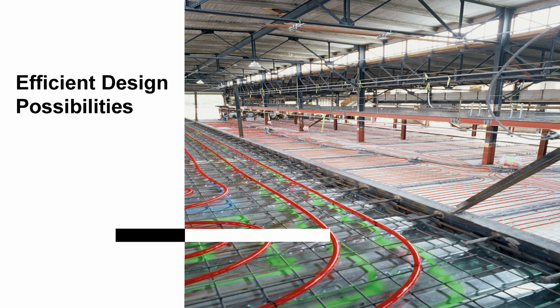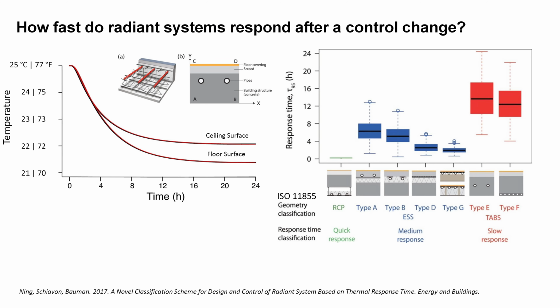So now we're going to talk about how high thermal mass radiant systems offer great design flexibility, especially as we transition to renewable energy sources and efficient HVAC equipment like heat pumps. As we mentioned earlier, high thermal mass radiant systems have the water tubes embedded inside the concrete layers, such as the structural slab, and this has lots of thermal inertia. As a result, it takes a very long time to cool down the concrete after we start circulating chilled water through it.